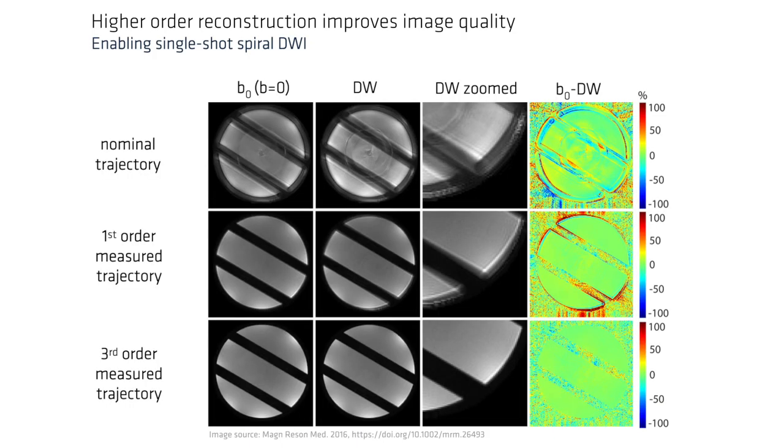In spiral imaging, the undesirable field terms result in blurred images. Here you can see the impact of using different measured field terms for reconstruction. Without any treatment of these undesirable field terms during reconstruction, the phantom is strongly blurred. First order correction reduces the blurring significantly. The blurring can be fully removed when also accounting for higher order fields.